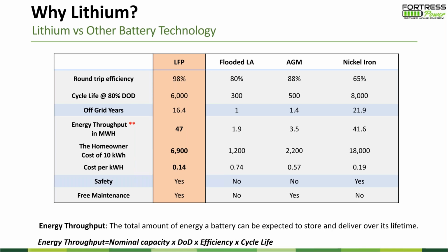Then life cycle at 80% depth of discharge: besides the nickel iron battery, which is super expensive because nickel is literally like money, all the others are way off. The lithium battery, especially lithium phosphate, the chemistry we're using, gives about 6,000 cycles. In off-grid years, theoretically lithium phosphate can last 16.4 years, since 6,000 cycles is calculated at one cycle per day. All the others just depend on how you use it - they don't last as long as you'd think.